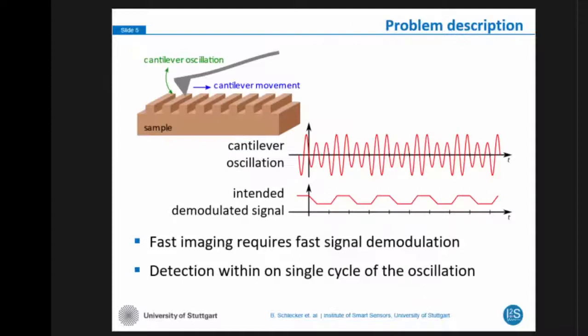In the tapping mode, the cantilever is oscillating near its resonance frequency while moving across the sample surface. You can see the resulting oscillation signal schematically for such a raster scan, where there is a higher amplitude and a lower amplitude depending on the height of the sample. For fast imaging, we want to have fast movement of the cantilever across the sample, which results in fast changes of the amplitude. We want to achieve detection of the amplitude within one single cycle of the oscillation.